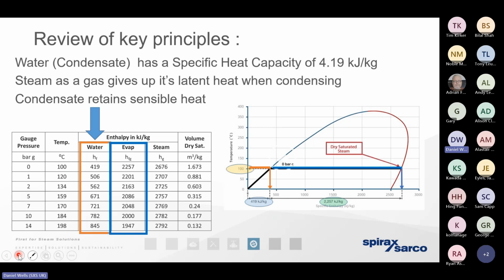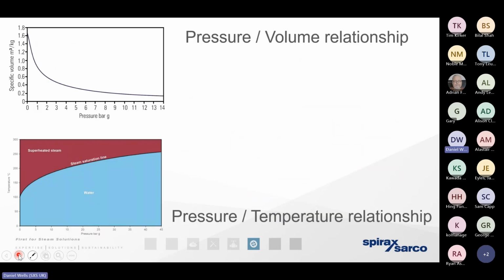But the box in orange really emphasizes that if we can recover the energy that is present within the condensate and get it back to the energy center, then we've got a really, really good head start in helping the boiler to react quickly and efficiently to produce the steam that is required. So there's a benefit in getting the condensate away, and there's a benefit in returning the condensate as well. We need to keep that in mind whenever we're moving forward to explore the areas for efficiency improvement. So we've also mentioned the pressure temperature and the pressure volume relationship in some detail.